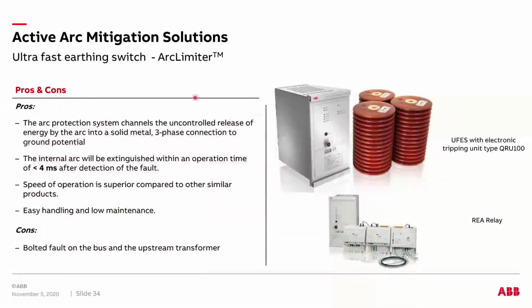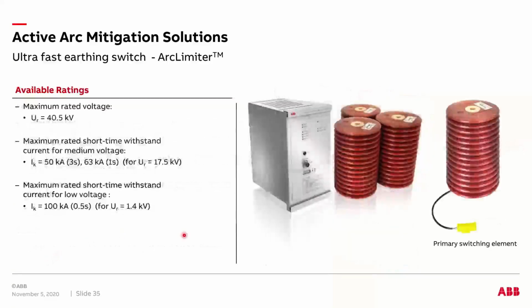So here is a reiteration of what the elements are. This is how the elements are going to look, and it's a very compact device, and we need one per phase, right? So it can be a solution for a new switchgear, either non-arc or arc resistant switchgear, or it can also be installed as a retrofit application, right? One of the things to keep in mind is it would create a three-phase to ground voltage fault on your bus, right? So that needs to be evaluated, whether your existing system should be able to withstand it for about 2 seconds. That should typically not be a problem.